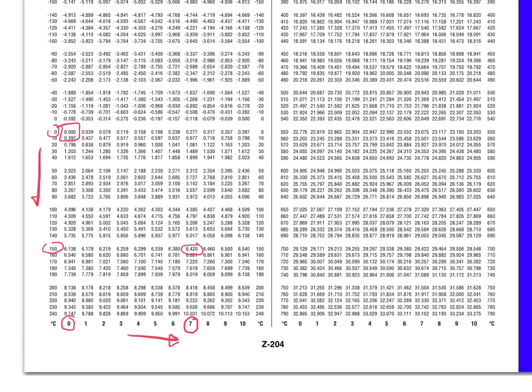You can also notice from the thermocouple table here that any temperature measured below the reference temperature, or in this case, if our reference temperature is zero degrees Celsius, any temperature below that will result in negative voltages, whereas any temperature that's measured above the reference temperature will result in positive voltages.